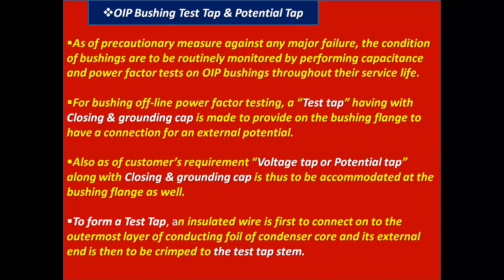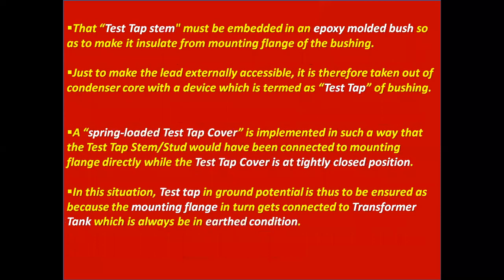To form a test tap, an insulated wire is first connected to the outermost layer of conducting foil of the condenser core, and its external end is then crimped to the test tap stem. That test tap stem must be embedded in an epoxy molded bush so as to insulate it from the mounting flange of the bushing. To make the lead externally accessible, it is taken out of the condenser core with a device which is termed the test tap of the bushing.